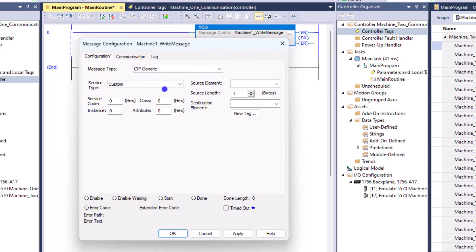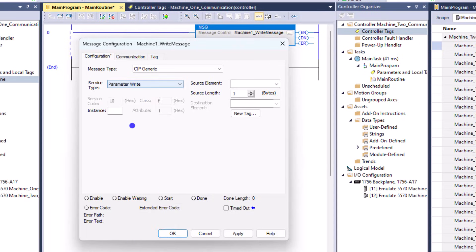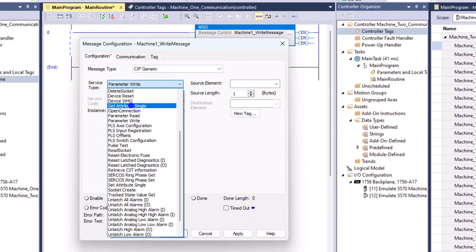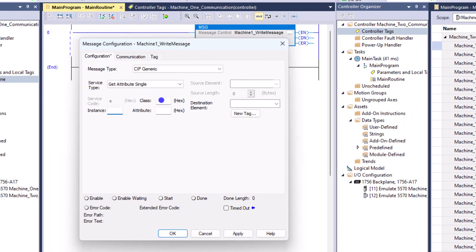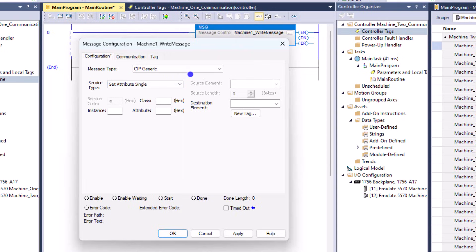Contrary to that, if I go to generic - and I've seen a lot of generic messages set up in the past - then you would come into service type. The service type gets to the point where you want to either read or write. If we did a write parameter, you would need to know the instance, and if you change to single attribute, you need the instance, the class, and the attribute. The easier thing for this illustration is to go to CIP data table.